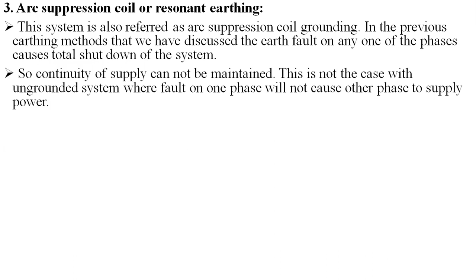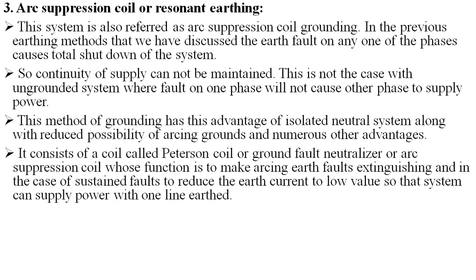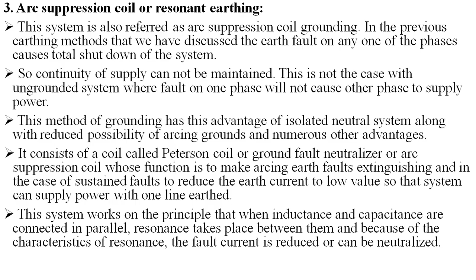It consists of a coil called a Peterson coil, ground fault neutralizer or arc suppression coil, whose function is to make arcing earth faults extinguish, and in the case of sustained faults to reduce the earth current to a low value, so that the system can supply power with one line earthed. This system works on the principle that when inductance and capacitance are connected in parallel, resonance takes place between them, and because of the characteristics of this resonance, the fault current is reduced or can be neutralized.